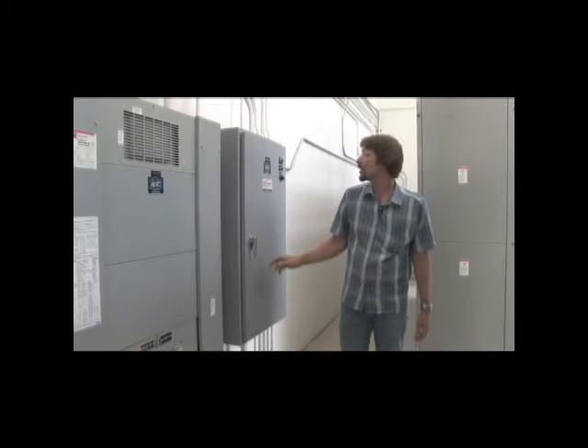So this is one of the two PDUs. Each of the server cabinets has a connection to each PDU, meaning that there's 4 power strips in a cabinet, 2 connected to this PDU and 2 connected to that PDU. Each of the servers has at least 2 power supplies.